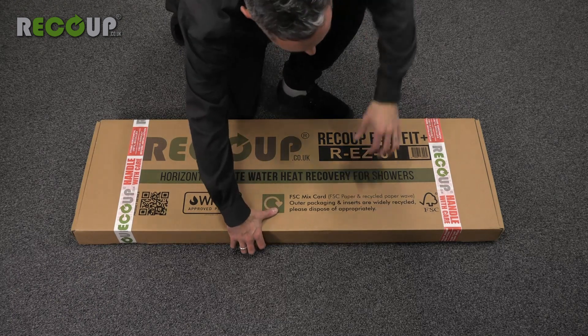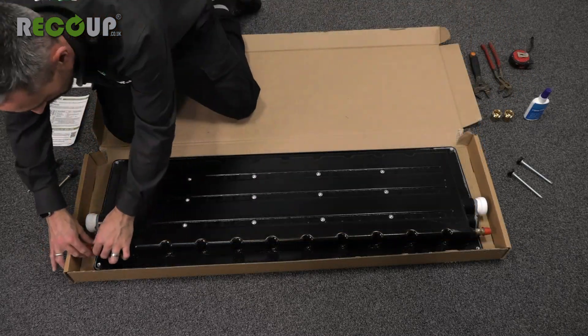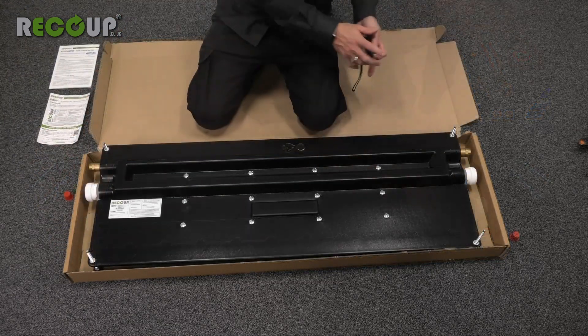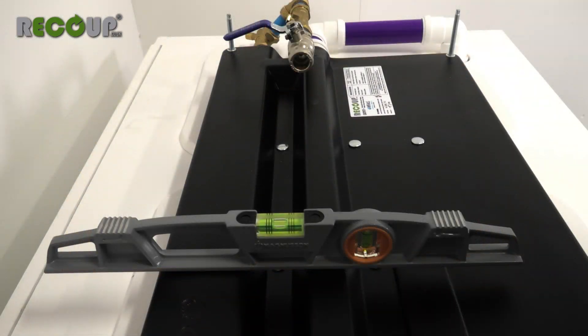It is recommended that the Recoup Easy Fit Plus remains in the box until it is ready to locate under the bath or shower tray. The mains water connections can easily be made while it is secure and less likely to be damaged. The legs should be adjusted to create between a 30 and 40mm fall across the length, and for the unit to be level across the width.